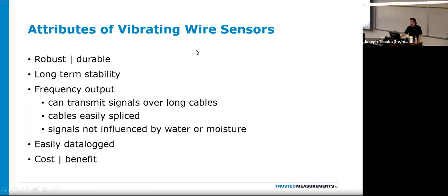Some attributes of vibrating wires, why they're so great, and why they're so well found here in the industry. They're very robust and durable. They're very stable long term. Very little drift. They can be permanently installed and be a reliable instrument for decades in some cases. The frequency output can be transmitted with very long signal lengths. Cables can be easily spliced, cut back, added onto. Signals are not influenced by water or moisture.